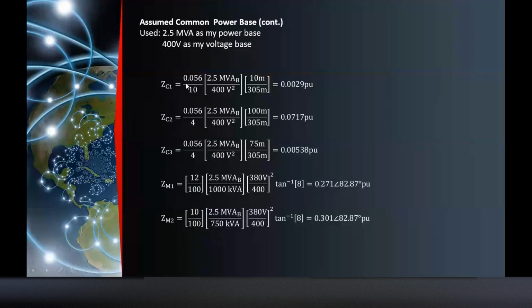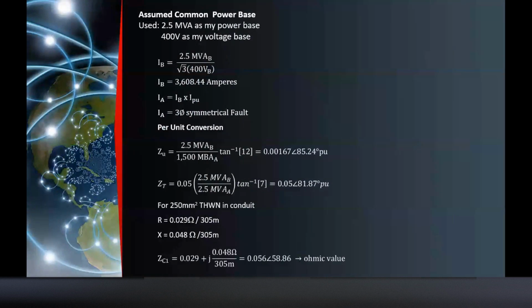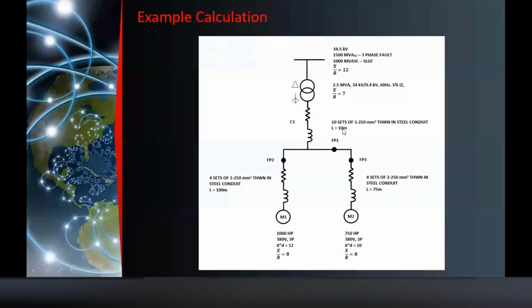For cable 1, this is the impedance, divided by the number of sets. Number of sets, from earlier. 10 sets. Okay? That is why you notice that when we set cables in parallel, we correct, let's say, the voltage drop, because the area gets bigger compared to when your cable is small. With a small area, you may have a drop. So you set in parallel, aside from ampacity, to correct the voltage drop from the sending end to the receiving end. Okay?